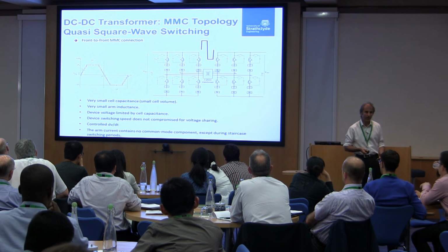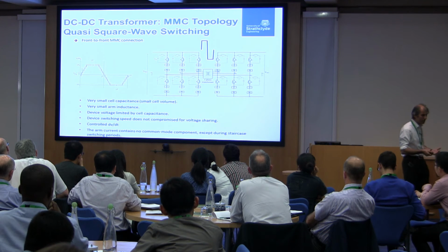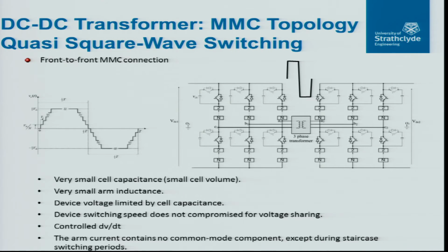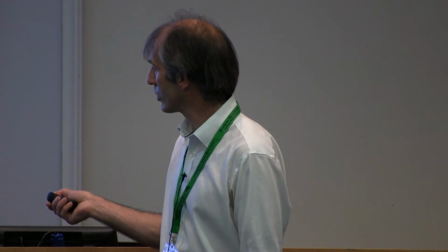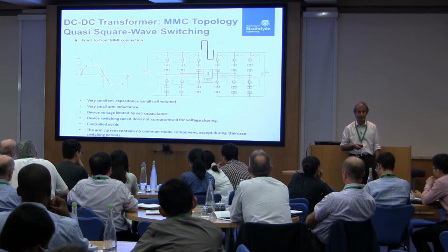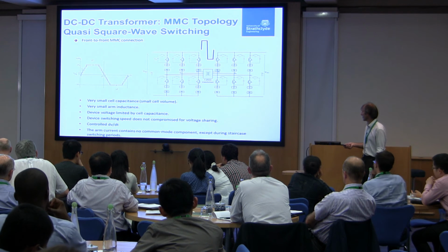So you can form something that looks like a dual-active bridge, but with a soft turn-on and turn-off edge to limit the high frequency imposed upon these windings, because trying to build that type of transformer at those power levels and subject it to very high dV by dt, not only have you got the EMI, you've also got the stray stresses on that transformer, which is big anyway, and now it needs to be designed for high frequency.